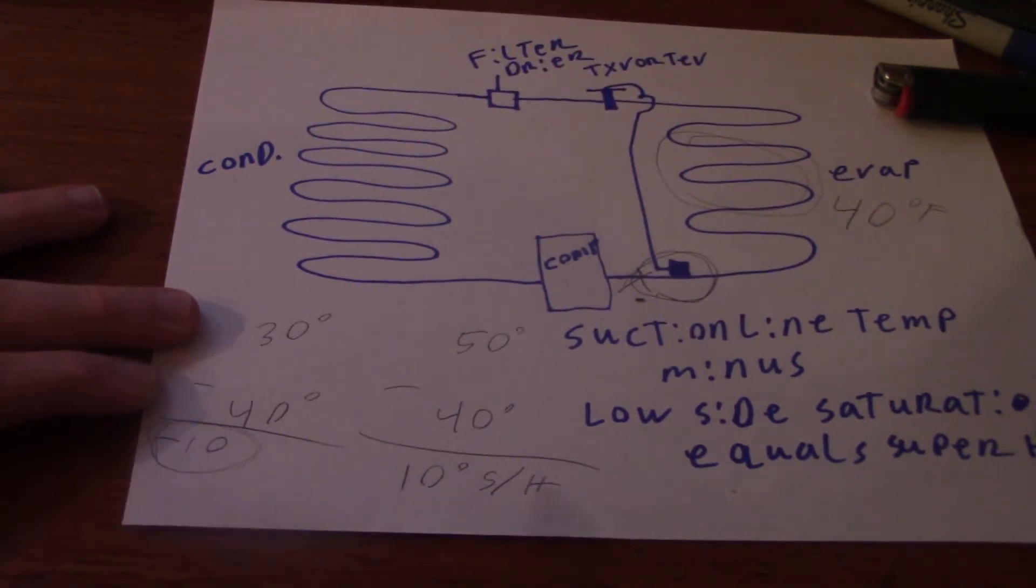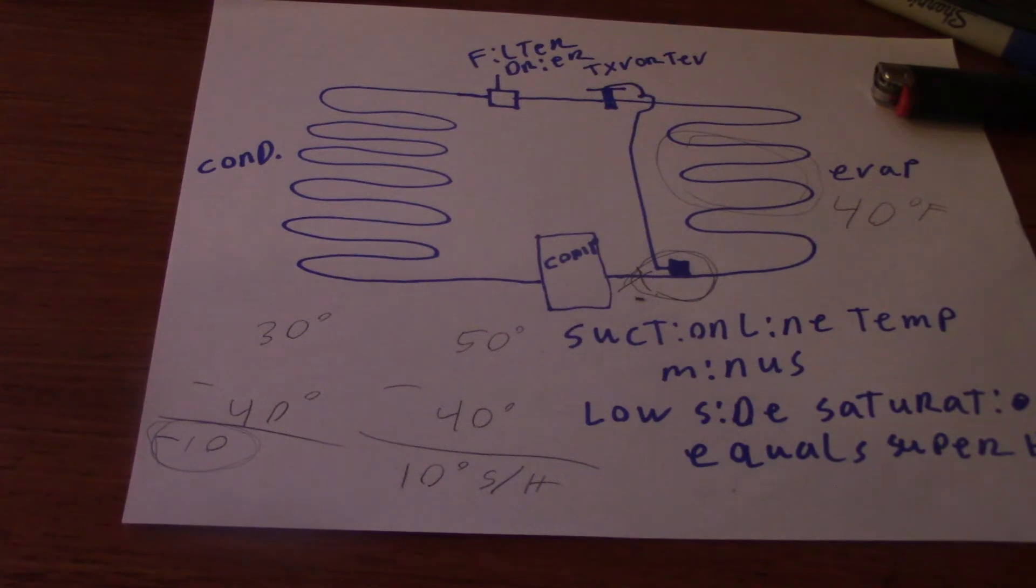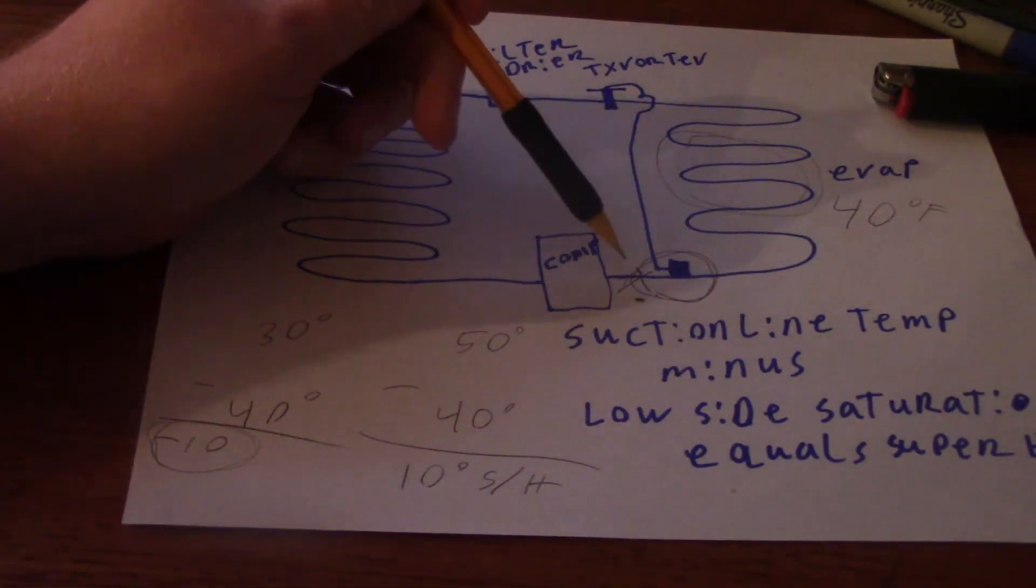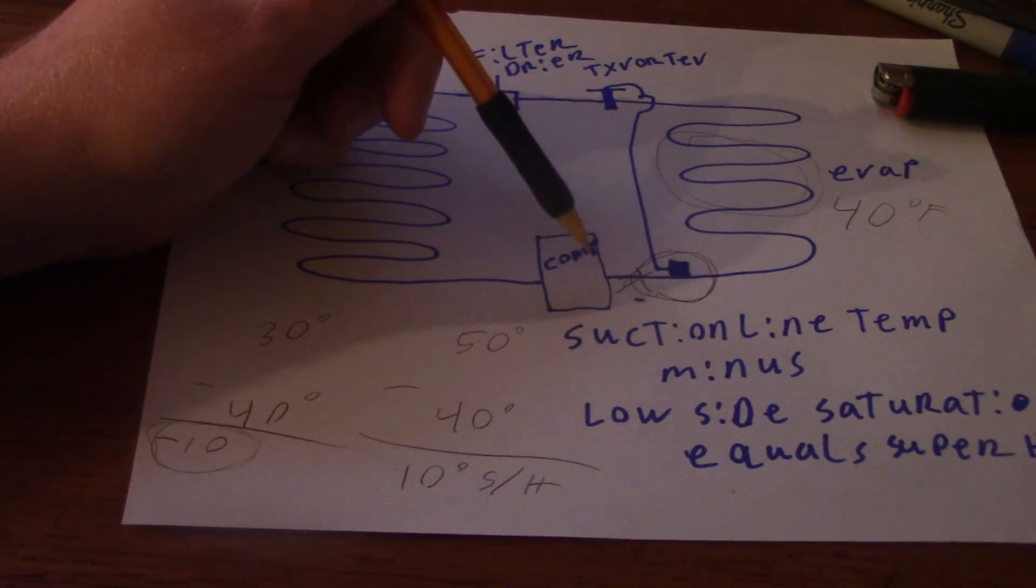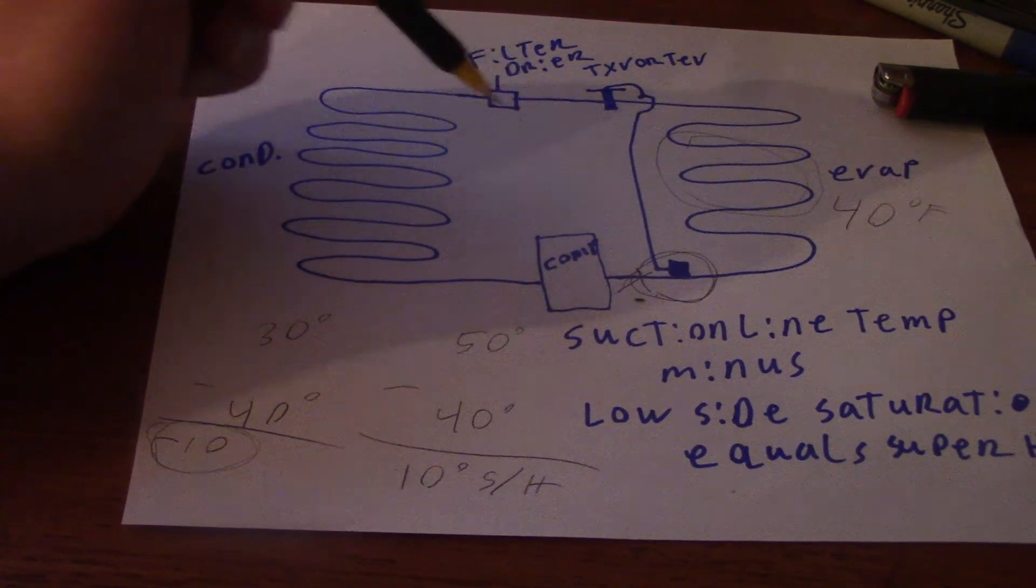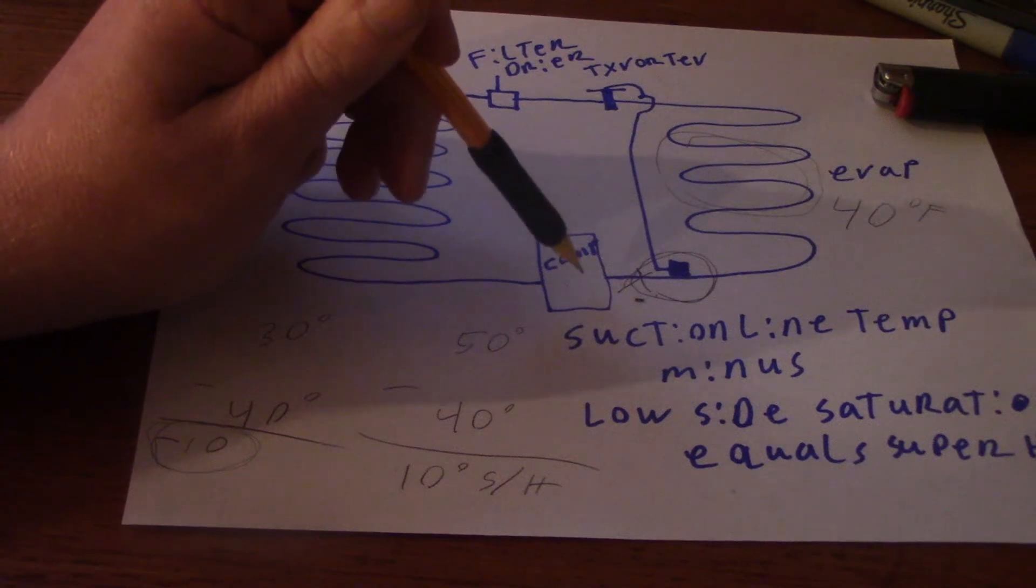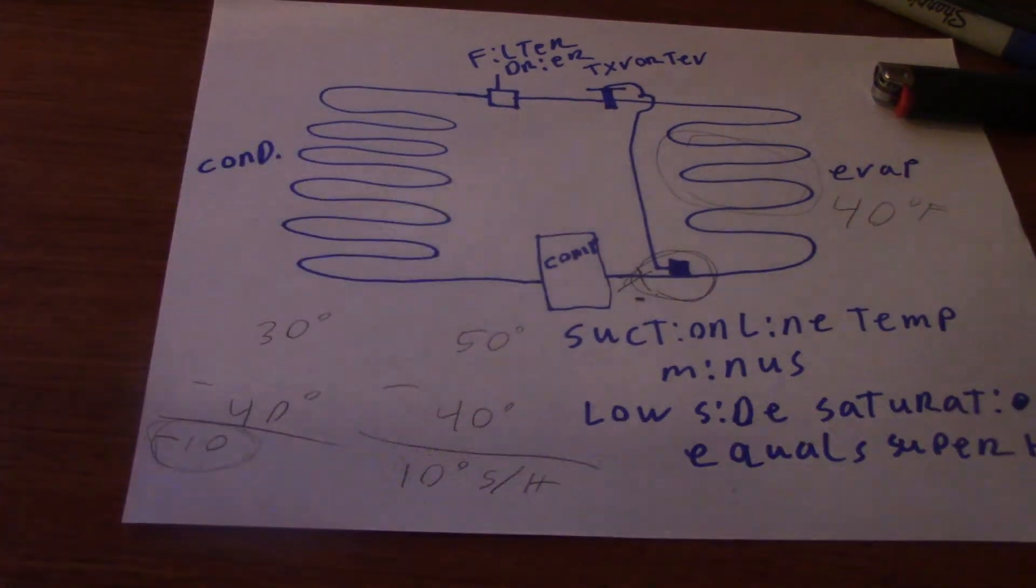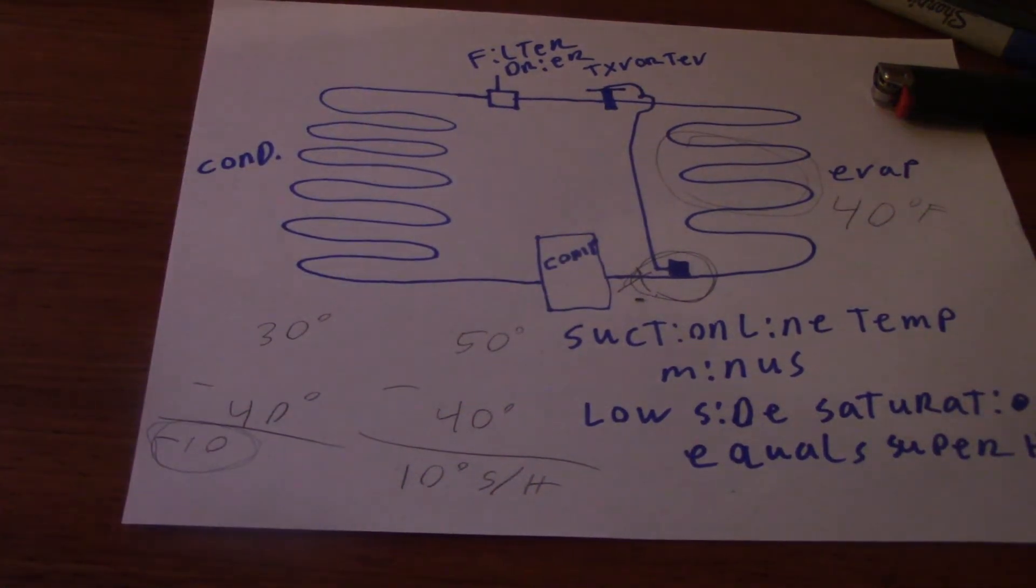What that means right there is you have no superheat going into the compressor. You actually have liquid refrigerant, and it's called slugging the compressor. That's what's actually going to happen, is this shell is going to start having, for the compressor is going to start having a liquid refrigerant in there. You were slugging the compressor, you're going to blow out your valves and pistons, all that stuff.